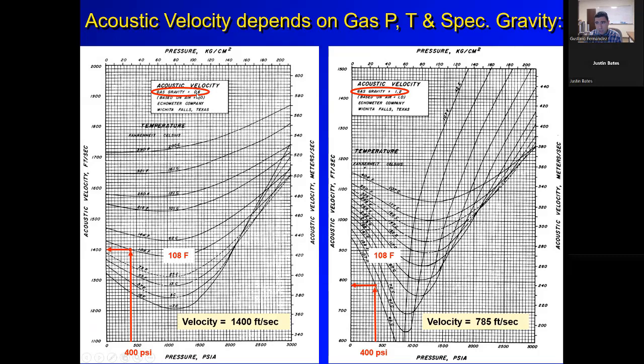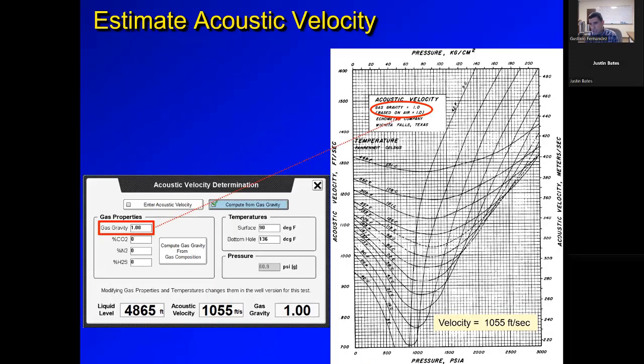And it's very sensitive. As I told you, 0.6 gas gravity with 400 psi at 108 degrees Fahrenheit results in 1,400 feet per second. Same pressure, same temperature, but a much heavier gas, and the resulting acoustic velocity will be even less than 800 feet per second. Those are the two far ends of the range, but this will be highly affected by the gas composition, so you don't want to just guess it. When you enter that information, gas gravity, pressure, and temperature, in the background, which you don't see, the software is calculating the resulting acoustic velocity. That's what the software is doing with that information.